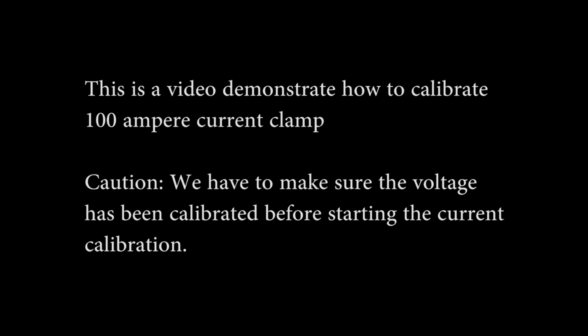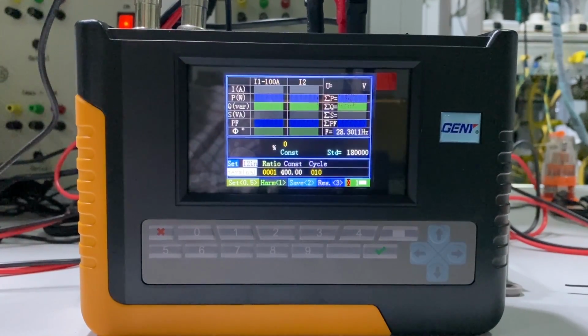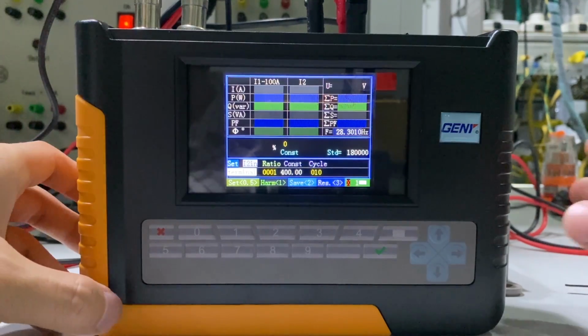This is a video demonstrating how to calibrate a 100 ampere current clamp. Caution: we have to make sure the voltage has been calibrated before starting the current calibration. Now we demonstrate the 100 ampere current clamp adjustment.